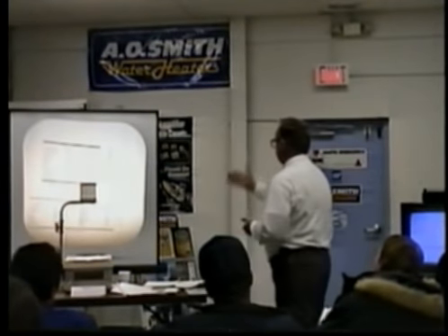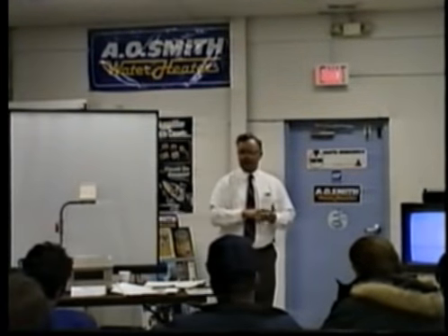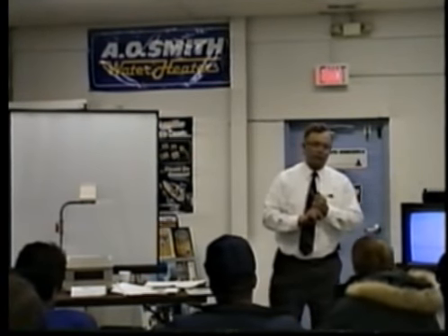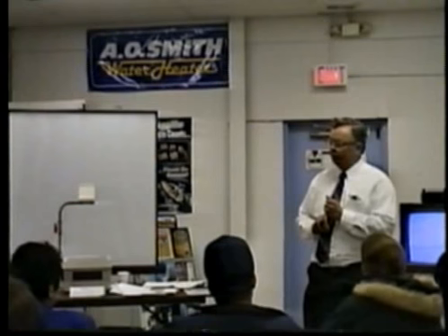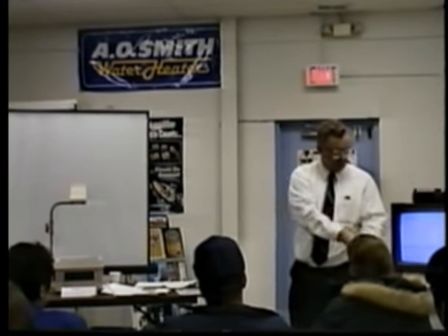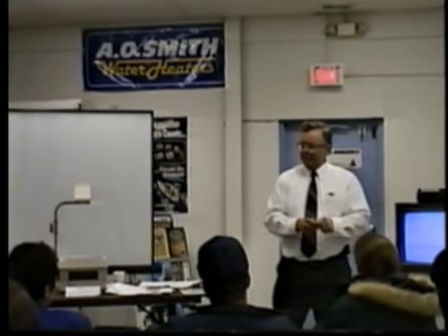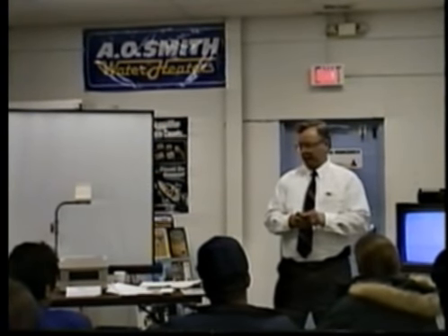But you see, ladies and gentlemen, we use water. Water's got a specific gravity of 1, and we use water in this business. Our instruments measure everything in a column of water. In other words, we can have negative pressures that pull, we can have positive pressures that push, but everything is measured in inches of water column.